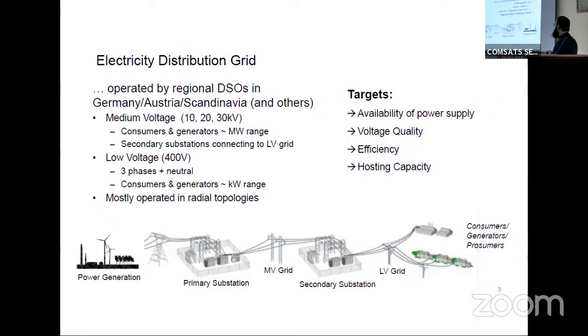From the primary substation, it goes to the secondary substations via the medium voltage grid. The medium voltage grid in Europe is 10, 20, and 30 kilovolts, whereas in Pakistan it is 11 kV, where they have different consumers, large consumers, big generators in the medium voltage range. The secondary substations connect to the low voltage side of the grid, and from there the electricity is transferred to the low voltage grid, and as in Pakistan, distributed to your homes, your companies, or wherever electricity is required.